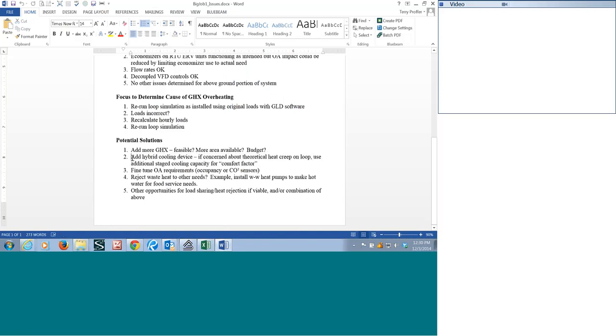If we have to go with the auxiliary cooling, that's going to get the system back to being reliable. But what else can we do? Well, we see a lot of times that outside air is a big issue on a commercial job, whether it's in the cooling or the heating mode. We often find economizers on ERV equipment locked open 100% of the time, 24/7, doesn't matter what the outside air temperature is. And what a lot of us do, of course, is put in occupancy or CO2 sensors to only use that much outside air that's required to meet code.